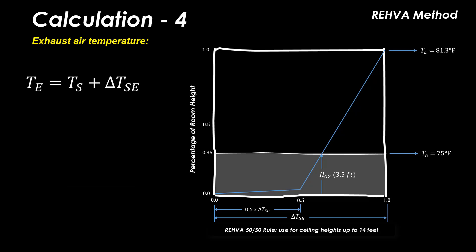The exhaust air temperature TE is calculated by simply adding the supply air temperature to the delta TSE calculated in the previous step. So 62 plus 19.3 results in 81.3°F.